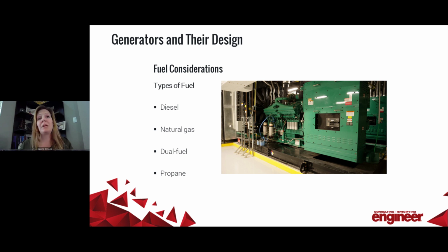The dual fuel begins to combine the best of both worlds, right? It's compression ignited engines that run simultaneously on the combustion of both diesel and natural gas. So the generator still maintains the ability to operate on 100% diesel if it's needed, but it also uses the natural gas. An advantage of these types of systems is that it could extend the runtime of the generator because you get two types of fuel. It reduces operational costs because natural gas is cheaper than diesel, and it's cleaner than its diesel-only counterpart. The disadvantages, and it's a major disadvantage here, is the cost. So that is why we're just not seeing it implemented too much into the hospitals.